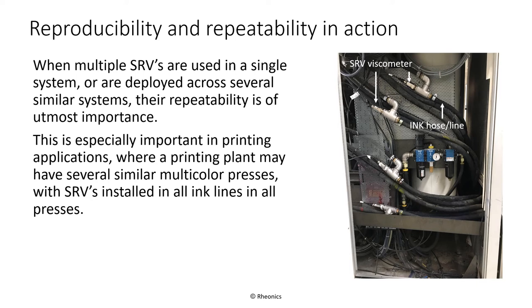It can be disconcerting for users accustomed to mechanical means of measuring viscosity to find the SRV's measurements to be very different from their lab measurements. What is crucial to maintaining constant properties of a process fluid are reproducibility and repeatability. SRV's high reproducibility means that two different SRVs in the same fluid will give the same reading — important when installed on parallel process lines or when replacing a damaged instrument. SRV's repeatability means it will maintain the consistency of a fluid's viscosity even over long production runs, and is a measure of the sensor's stability.